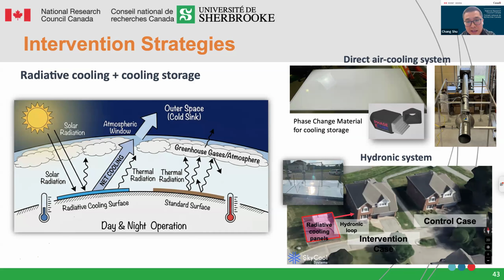So on the right side is an example from our test houses. One is a direct air cooling system, which cools air directly and connects with phase change material to see how they couple with each other. The other is a hydronic system, which cools water and supplies it to a heat exchanger in the air handler to cool down the building.